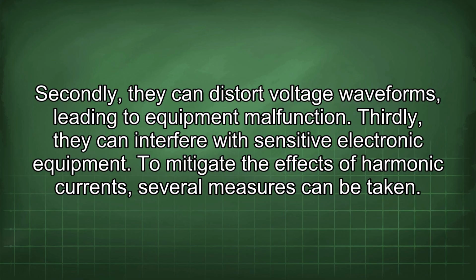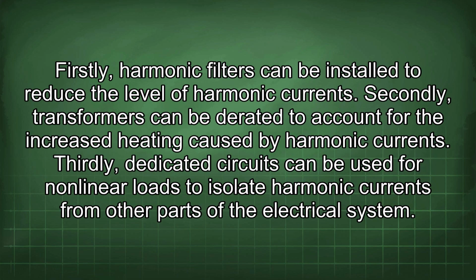To mitigate the effects of harmonic currents, several measures can be taken. Firstly, harmonic filters can be installed to reduce the level of harmonic currents. Secondly, transformers can be derated to account for the increased heating caused by harmonic current. Thirdly, dedicated circuits can be used for nonlinear loads to isolate harmonic currents from other parts of the electrical system.